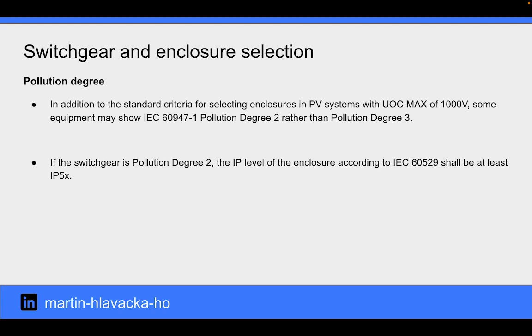In addition to the standard criteria for selecting enclosures in PV systems with open circuit maximum voltage of 1000 volts, some equipment may show pollution degree 2 rather than pollution degree 3. If the switchgear is pollution degree 2, the IP level of the enclosure according to IEC 60529 must be at least IP50.